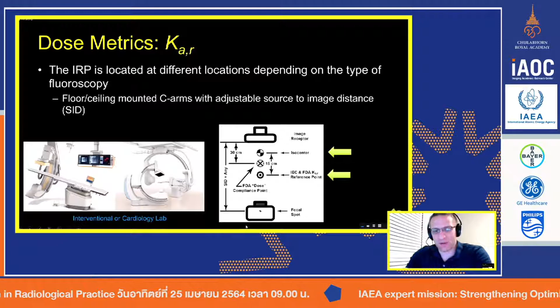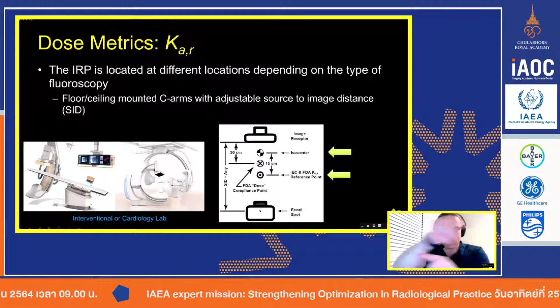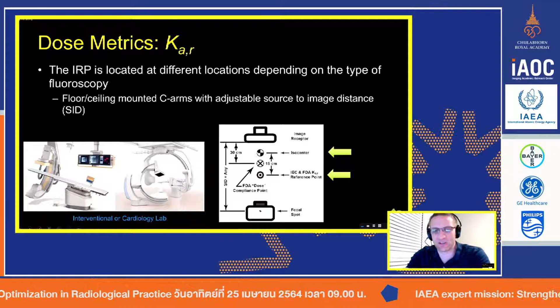So what do I mean by interventional reference point? In this example, I'm just going to use a C-arm, and this is an interventional system, but I'll show you where the interventional reference point is for all types of fluoroscopy systems in a minute. But in every one of these C-arm systems, you have the detector on one end, of course, and the X-ray tube on the other side. And there's going to be an isocenter. That's the point on these C-arms that the C-arm itself will rotate around a patient. That's the point you want to stick dead center of the patient so that we can get the right radiation dose to the patient, good image quality.